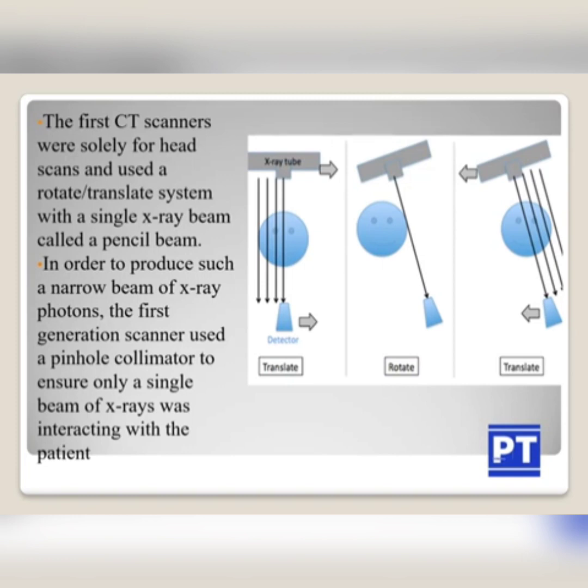You can see the X-ray tube as well as the detector — there was only one detector and you can see the linear movement in the figure. After one completion, the X-ray tube rotates. The first CT scanner used a rotate-translate system with a single pencil beam. In order to produce such a narrow beam, the first generation scanner used a pinhole collimator to ensure only a single beam of X-ray was interacting with the patient.